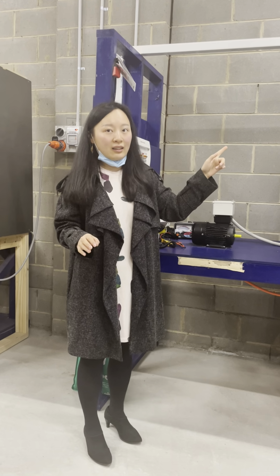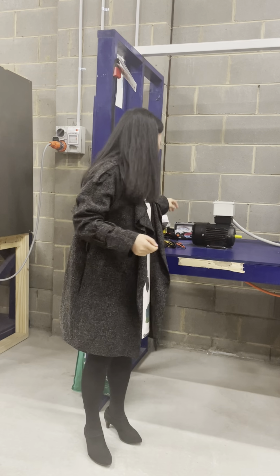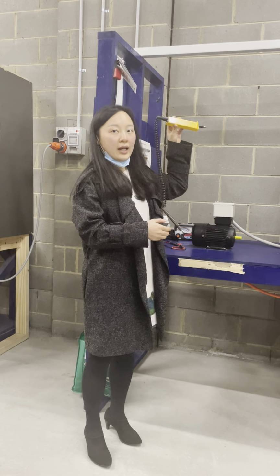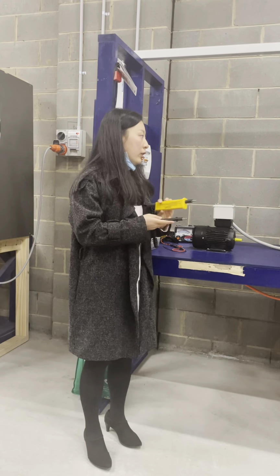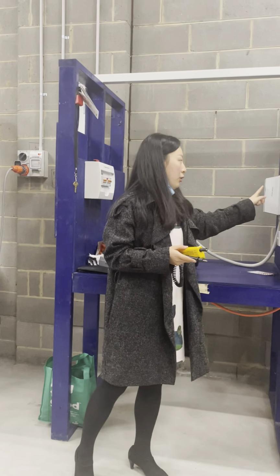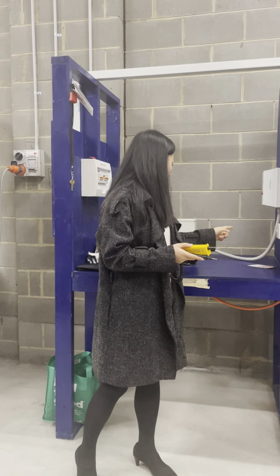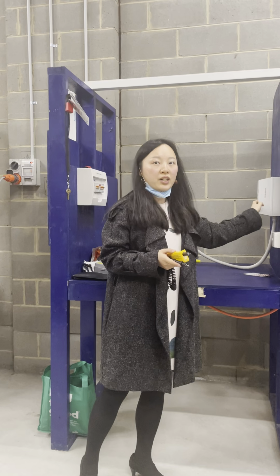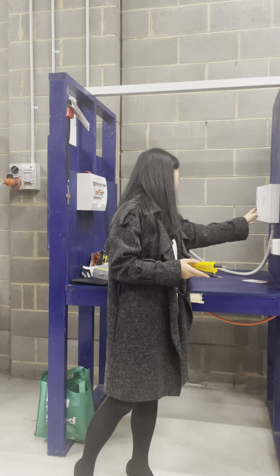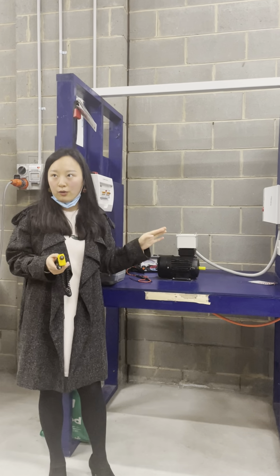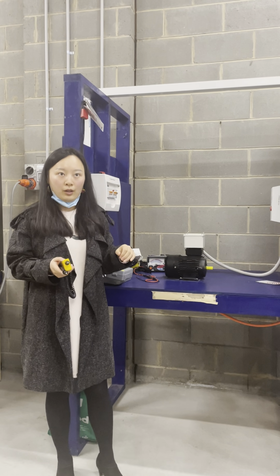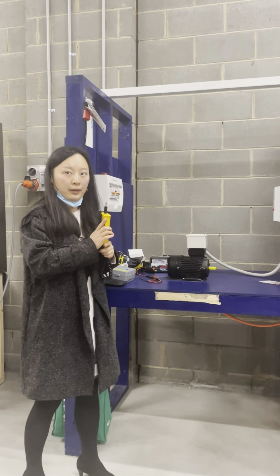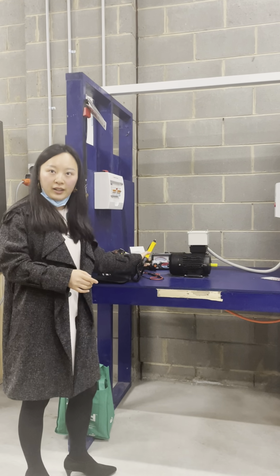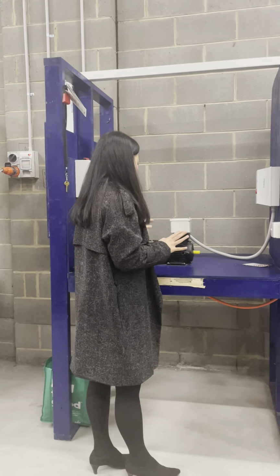If it is other applications, you need to use this voltage meter to test. But because this is a motor, this is the second time you're going to use this button, so it's rotating, correct? The direction doesn't matter, but it's rotating. That already confirms there is voltage on the existing terminal, so you don't need to use this for this step. Is that clear so far? Okay.